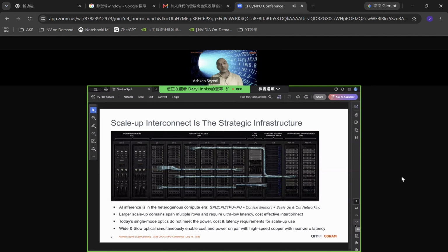You know, in this form factor, obviously it's all copper, and that's why we have built dense racks. But as that connection becomes optics, as the accelerator to the L1 switch connection becomes optical, you have to ask yourself, do I need to build such a dense rack when I'm able to go now 50 meters or 60 meters reasonably cheaply? Then we are entering perhaps a new era of disaggregated rack design. We're not there at all today. I do want to acknowledge that from a systems perspective, even if you enable that, it is too disruptive.